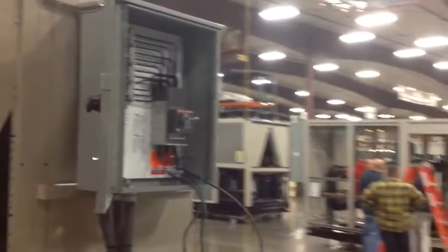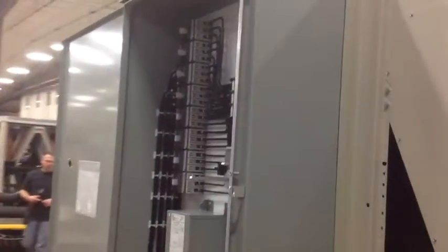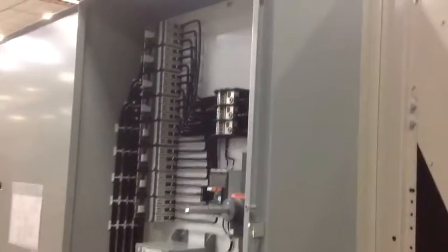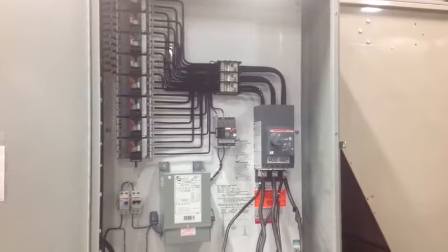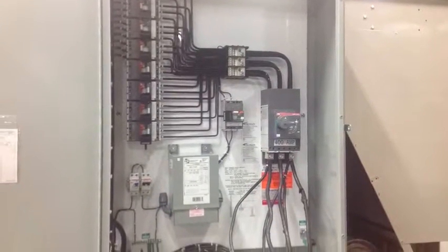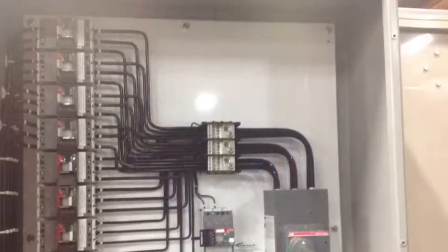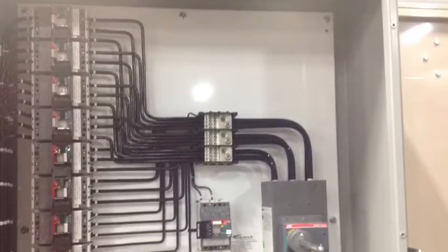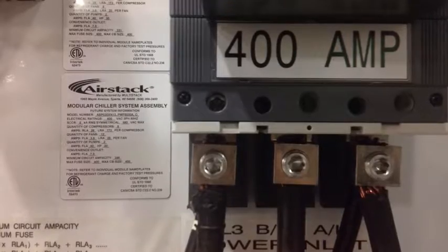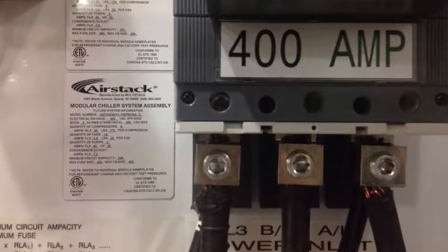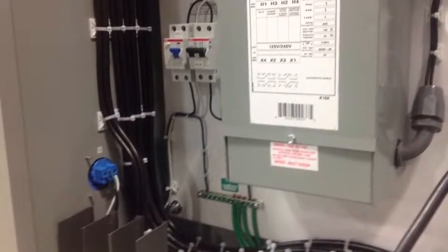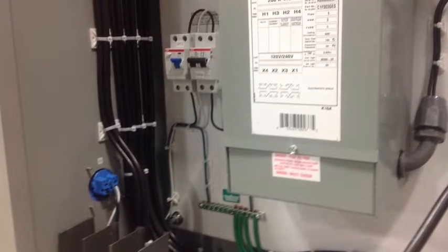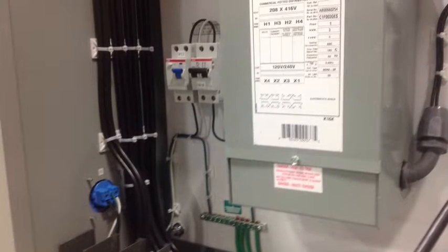Panning right from the 3 module array to the main array, this is the single point power connection for both pumps, 4 mechanical modules, and the future 2 free cooling modules. This panel also includes a transformer for a convenience outlet. The power distribution block distributes power from the door interlock disconnect switch marked with the 400 amp service, and we see the nameplate data in the background. And now a close-up of the convenience outlet.